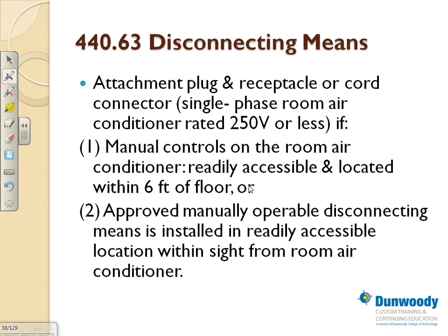Disconnecting means: attachment plug or cord, single phase room air conditioner up to 250 volts. So you can have the plug as your disconnecting means. Readily accessible and located within 6 feet of the floor, that disconnect and the plug. Or an approved manually operated disconnecting means installed in a readily accessible location within sight of the room air conditioner. So if you have a plug-in, you can use the plug as your disconnect. You can have a switch attached to the equipment, but it has to be accessible and not more than 6 feet off the floor. You can have a receptacle 6 feet and down and act as your disconnect, the receptacle plug disconnect.